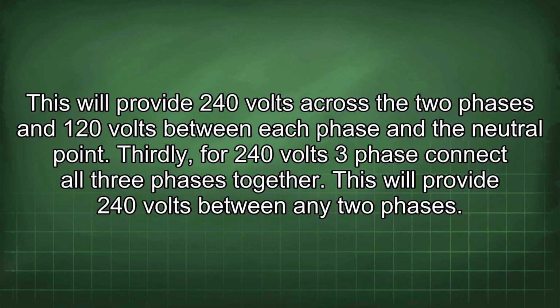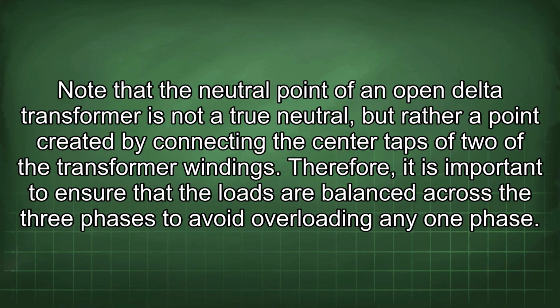This will provide 240 volts across the two phases and 120 volts between each phase and the neutral point. Thirdly, for 240 volts three-phase, connect all three phases together. This will provide 240 volts between any two phases. Note that the neutral point of an open delta transformer is not a true neutral, but rather a point created by connecting the center taps of two of the transformer windings.